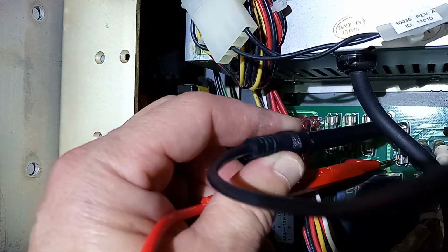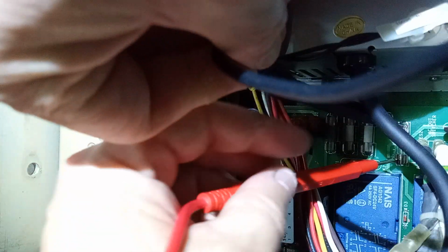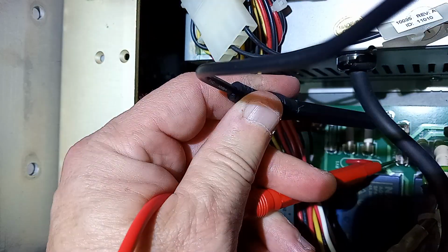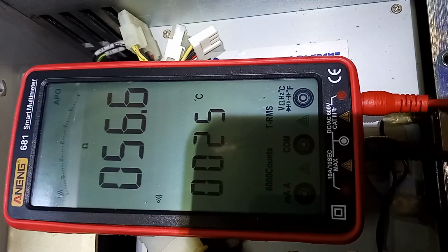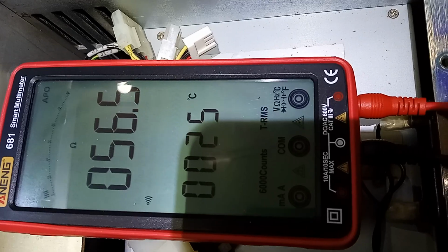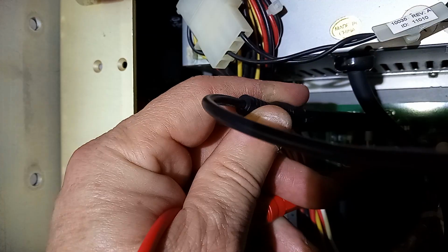Now this one's not giving me a complete short - it's giving me 56 ohms, so it's not open. It's almost a short, so it might operate that way. The E-stop is working fine, but giving 56 ohms, which is almost a short. So we're not going to touch that one because it's operating correctly.